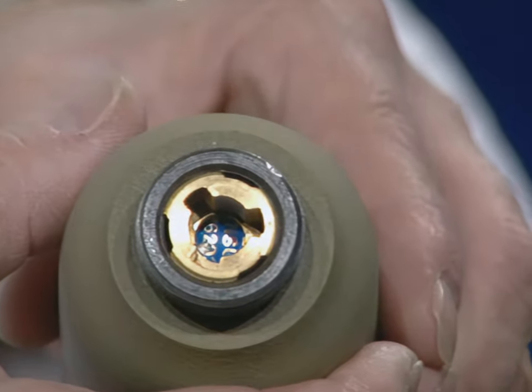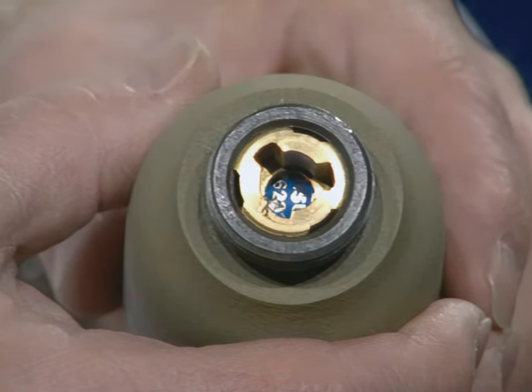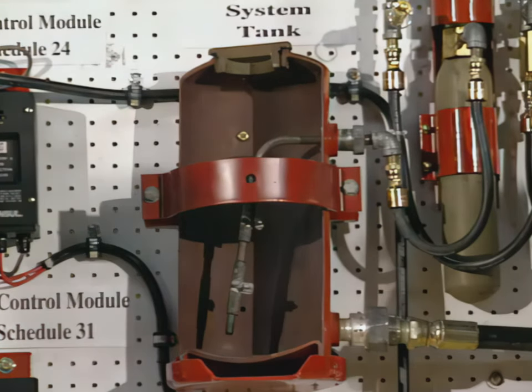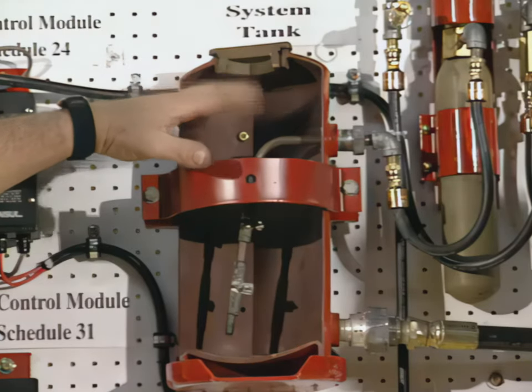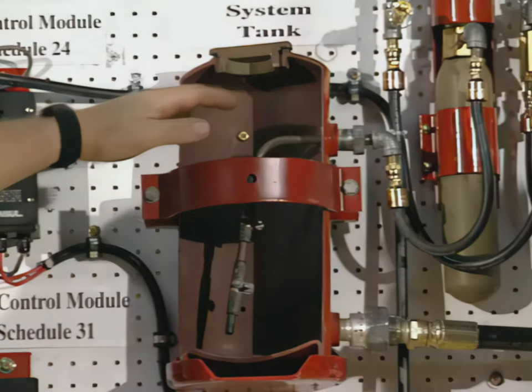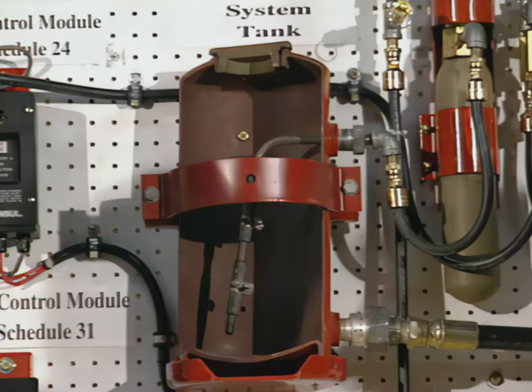That weight includes the cap. Also, this actuation canister must have this seal — Ansul's is blue. Each one of these tanks, the labels tell you how much chemical goes into these tanks, poundage-wise. Open up the top; a lot of times because of the chemicals settling as the vehicle's moving, it should not be more than three inches below the mouth of that canister.